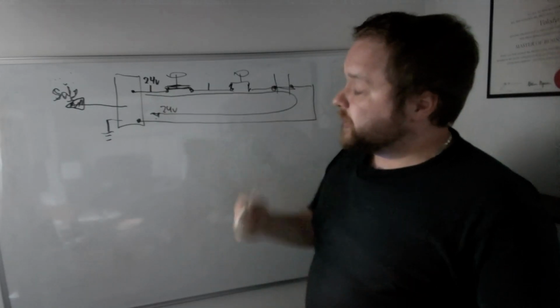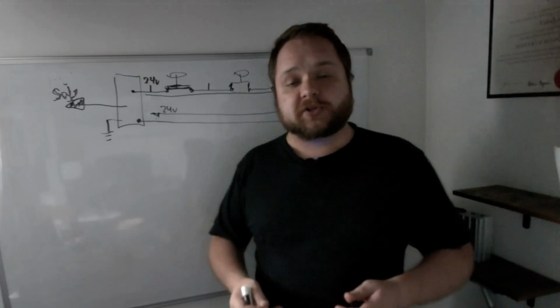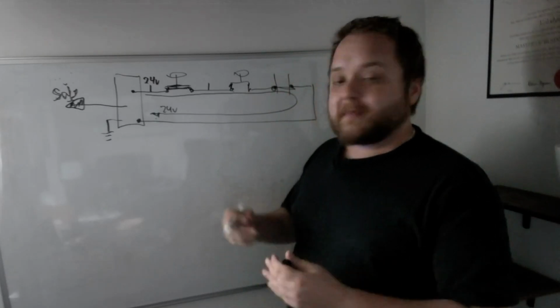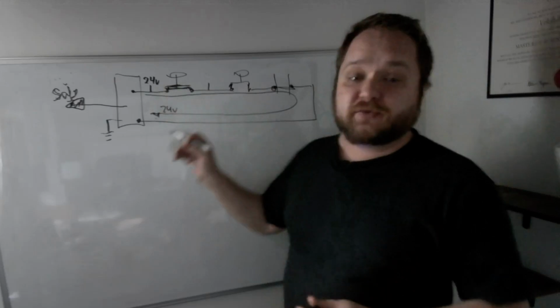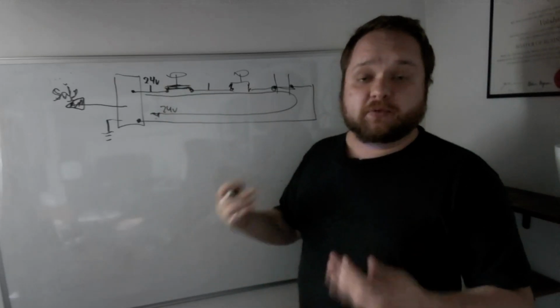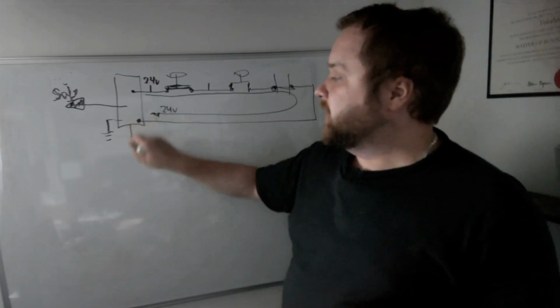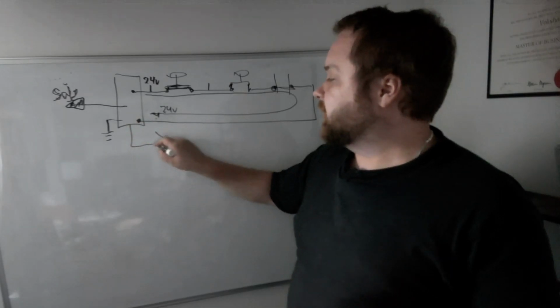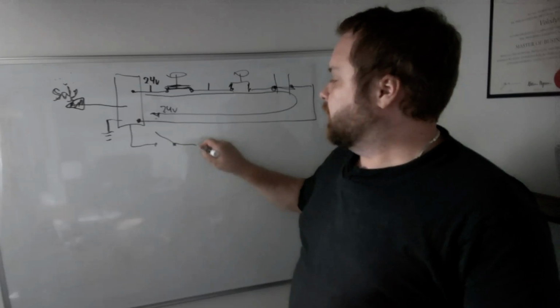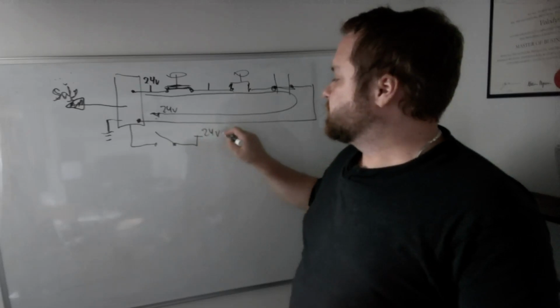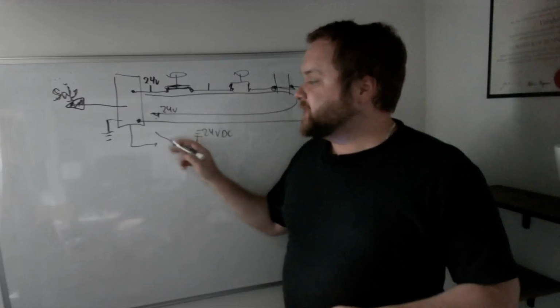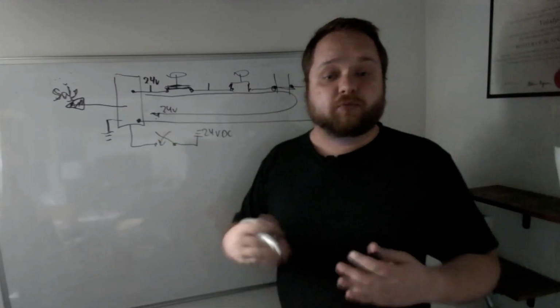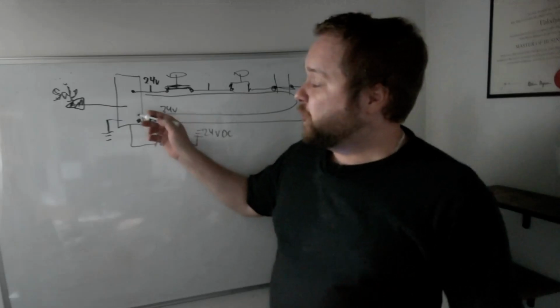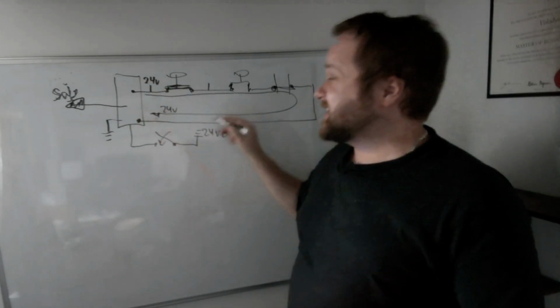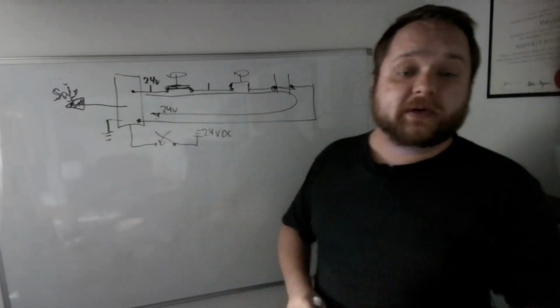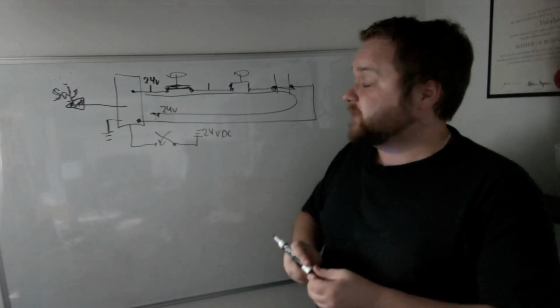Now, let's introduce another component. So in most applications, the safety relay is not going to automatically confirm that it is safe to operate. A lot of times you have what's called a reset circuit. So here, in its most basic form, you can either have a switch or a push button, but all you have here is 24 volts DC. And basically, once you complete the circuit by pushing a reset button, you're going to allow the safety relay to check that the status is indeed safe, and we can now operate the equipment associated with that specific safety relay.